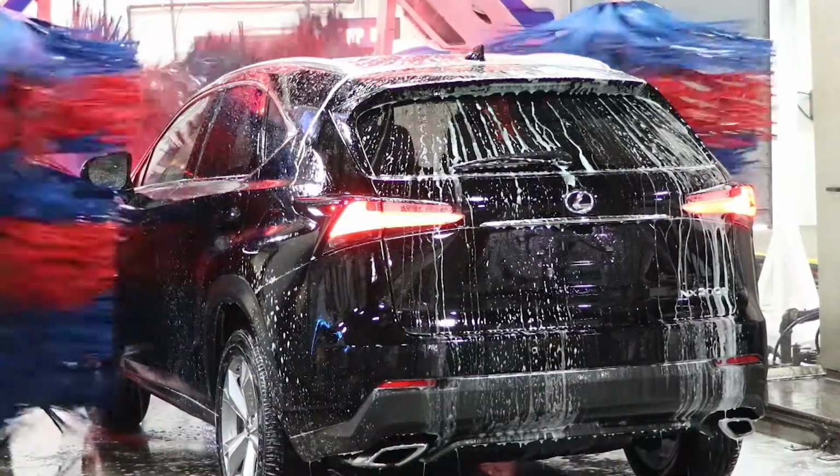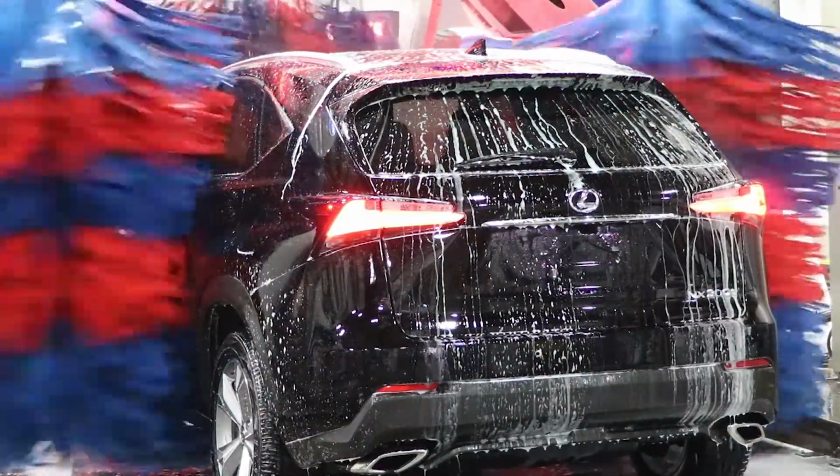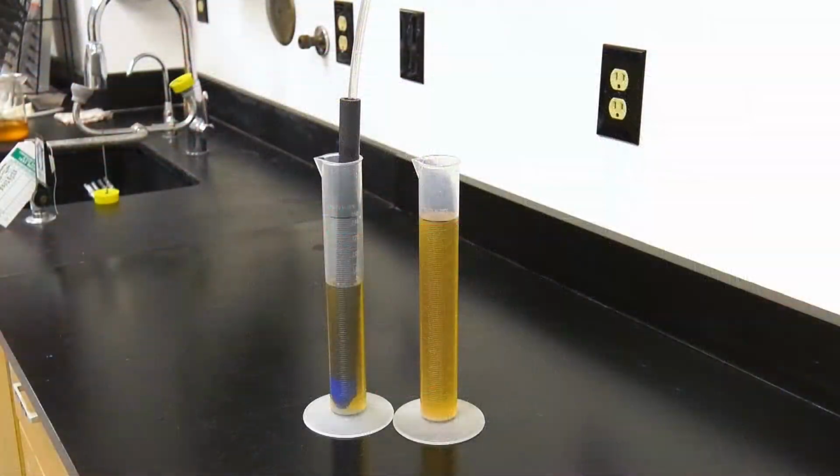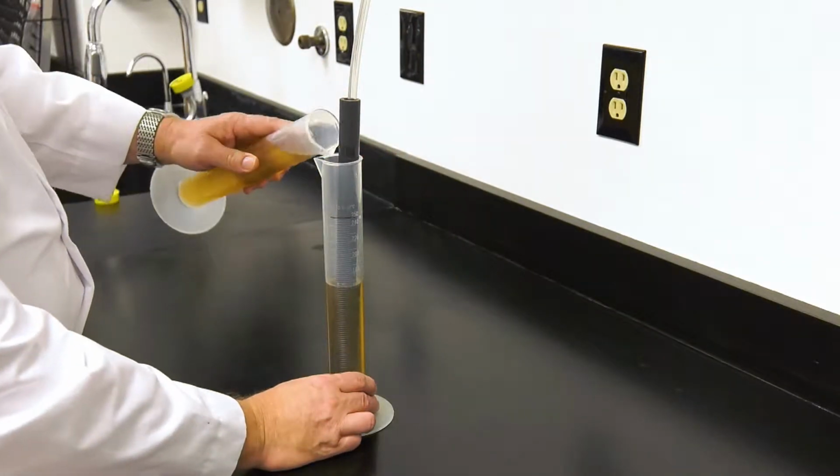Perform a test wash or activate the chemical test function for the time it is typically activated during a wash. The liquid level in the cylinder with the foot valve should be below 250 milliliters. Leave the manifold foot valve in the cylinder.